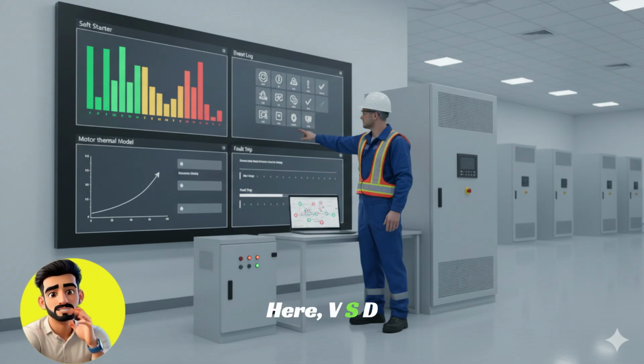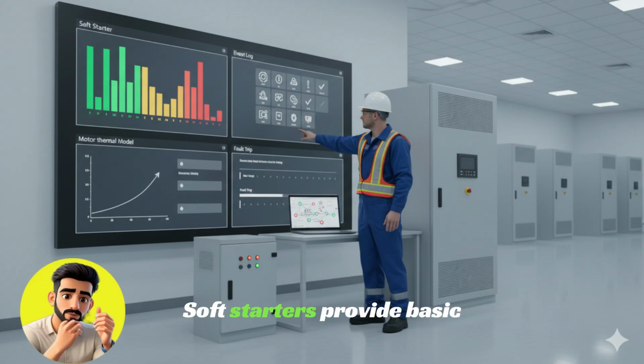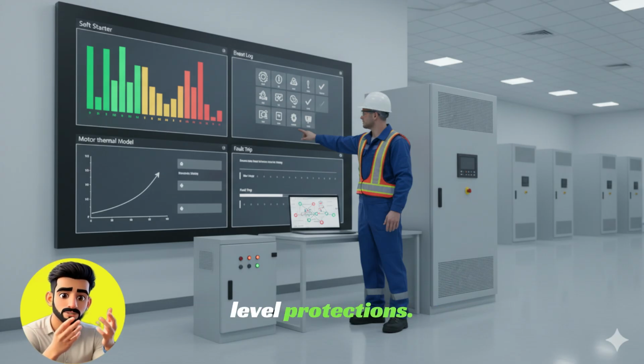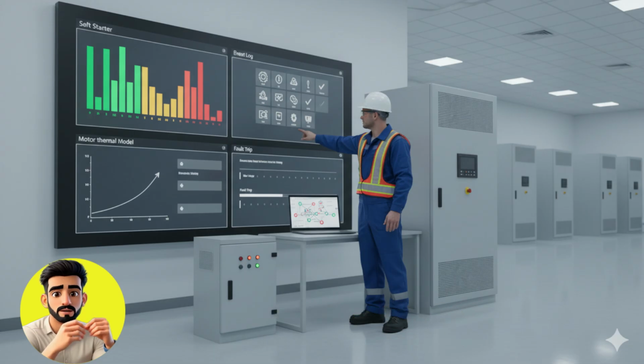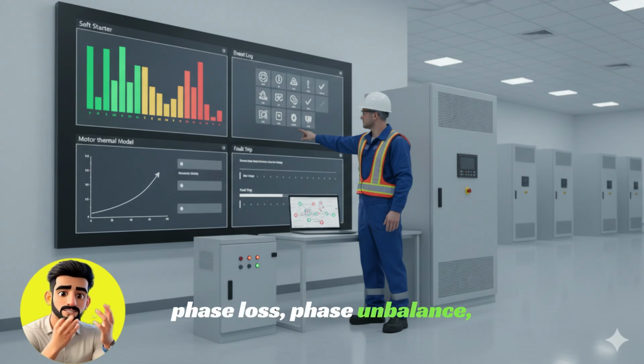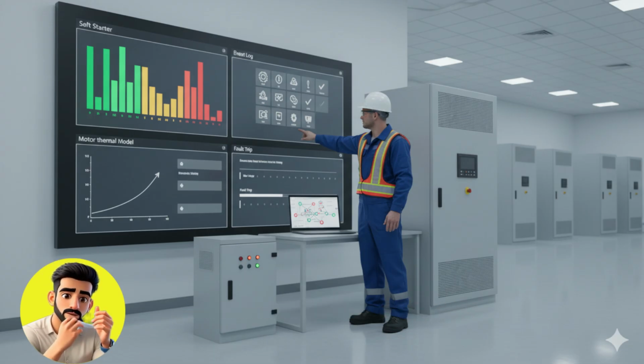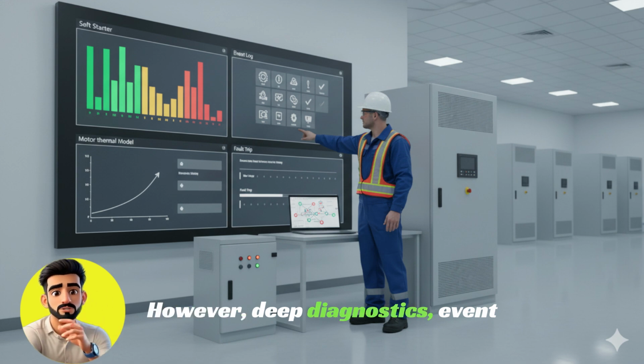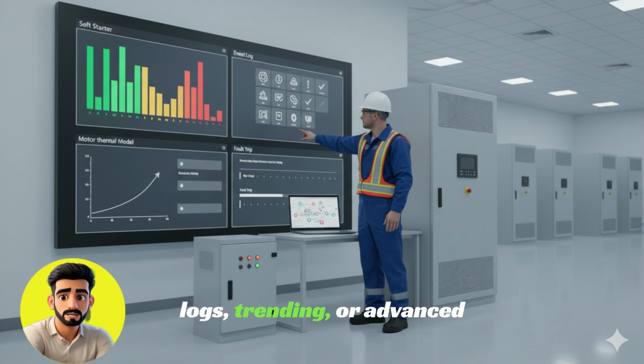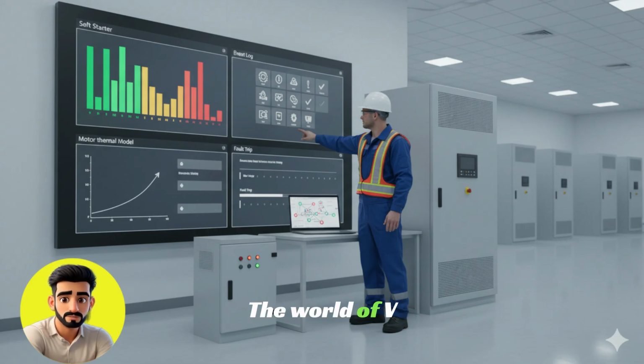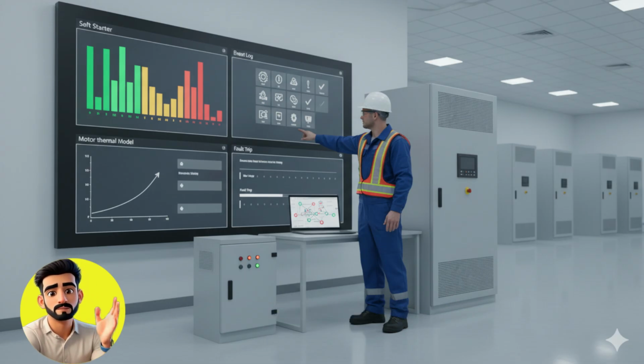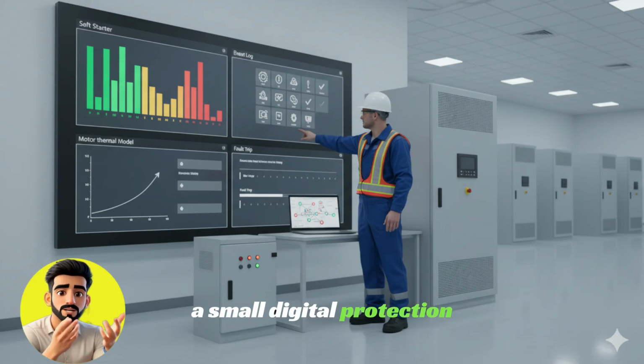Here, VSD clearly wins. Soft starters provide basic level protections, such as overload protection, phase loss, phase unbalance, and sometimes ground fault. However, deep diagnostics, event logs, trending, or advanced thermal models are normally limited. The world of VSD is completely different. VSD becomes a small digital protection center.